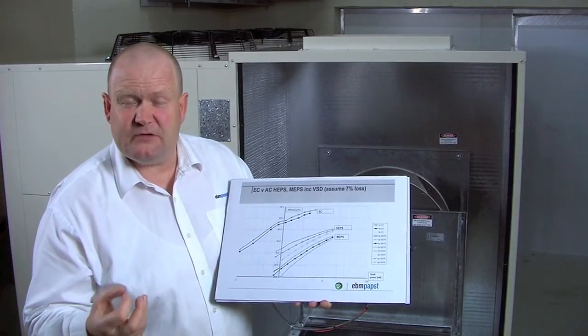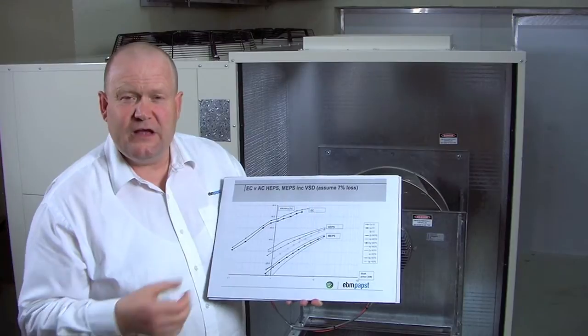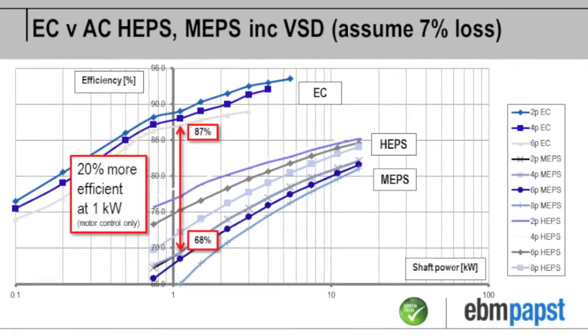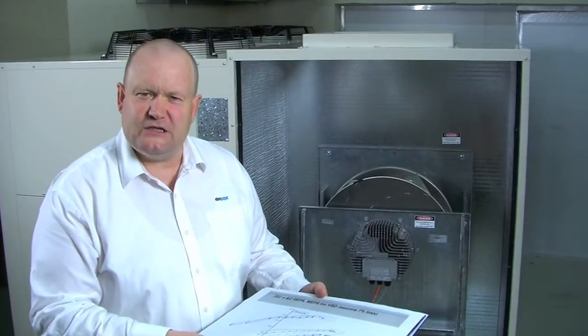EC is a permanent magnet motor with inbuilt speed control. And here you can see that the EC motor is between 15 and 20 percent more efficient than the AC VSD couple. Now that's really important as a drive mechanism in increasing energy efficiency.